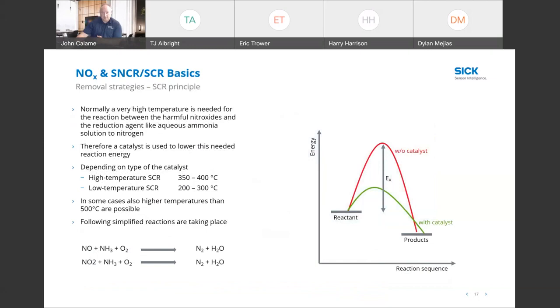So the SCR principle, we are actually using that catalyst as well as the ammonia injection into it. And what we're doing is measuring the ammonia slip that comes through. What we call ammonia slip is this: you want enough ammonia in there to fully react and remove all of the NOx. The only way to make sure you have enough in there is to have a little bit of residual on the downstream side that's going to break through. So we're measuring that really low level breakthrough, to make sure that you have enough ammonia along with the catalyst to effectively remove the NOx.